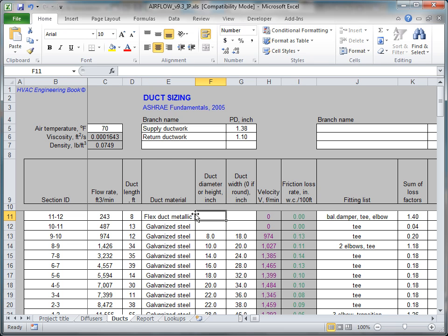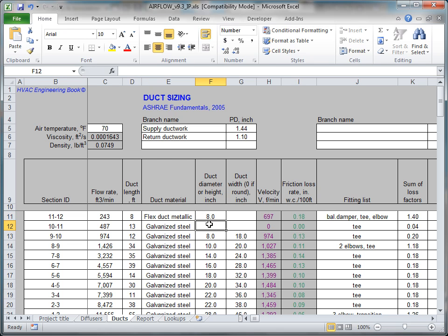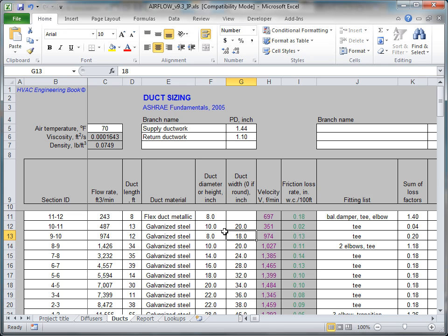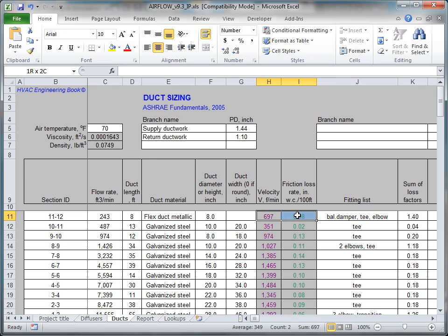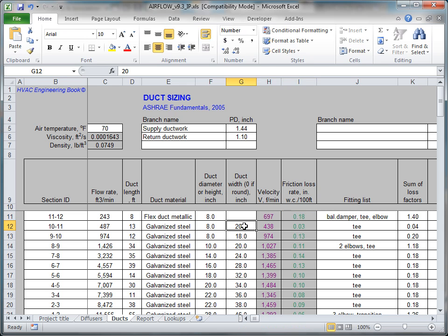In the next two columns, select a diameter for round ducts, or height and width for rectangular ducts. The code will immediately return the friction loss rate and air velocity. Change the duct size until the values fall within a desired range.